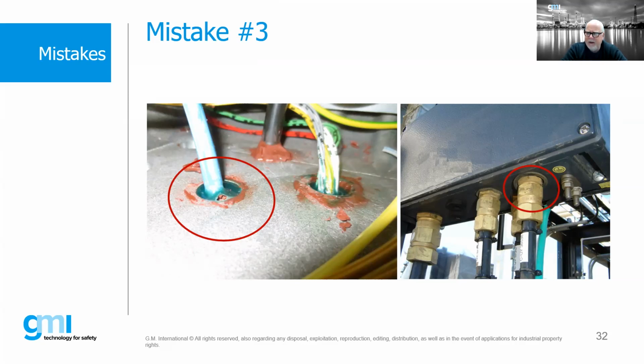However, if we look very, very closely, we see that that IP washer actually looks a little bit too big for this application and is not providing any protection whatsoever. So some of these little things are things that, again, you wonder what an inspector is doing. This is the stuff that we're looking for, right? We want to make sure we check this stuff out. And that's why we are usually not well received by clients when we come in and we start checking all this stuff. So again, if we do this and we address it before it gets into the field, then a lot of these problems get alleviated.